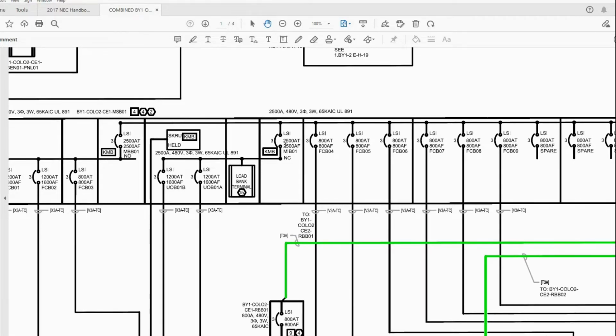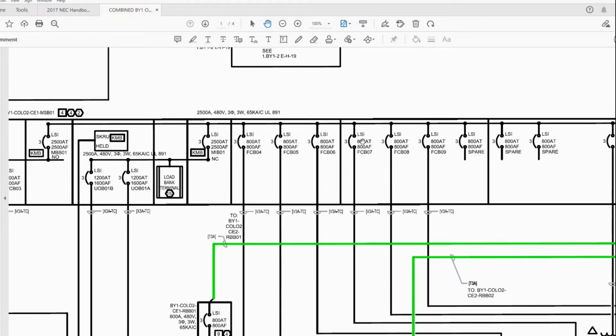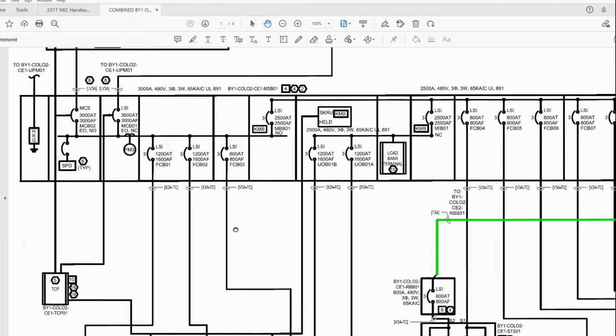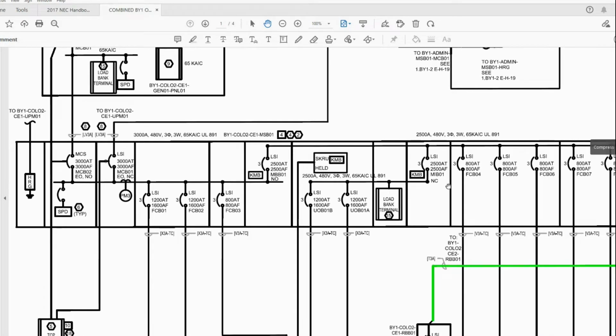One of the things that we want to do is to be able to close both of these breakers at the same time, because if we open them both at the same time, we lose our main bus breaker and the MIB breaker, and we lose power to our critical bus. We do not want to lose that, because that's where all our servers are being fed from. So if we look at this right here, we have power coming in from our utility, goes across, and it feeds in through our MBB downstream to our critical bus.